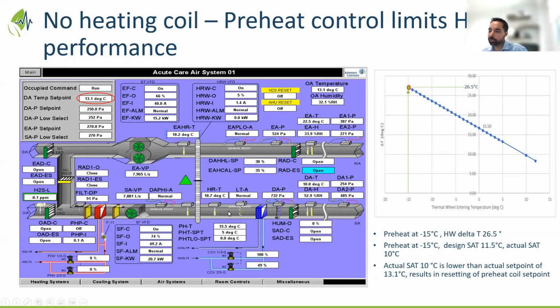However, this is sort of a unique scenario in this facility, because they did not have a heating coil downstream. They could not maintain the supply temperature, so they had to increase the preheat set point higher to achieve that discharge air set point.